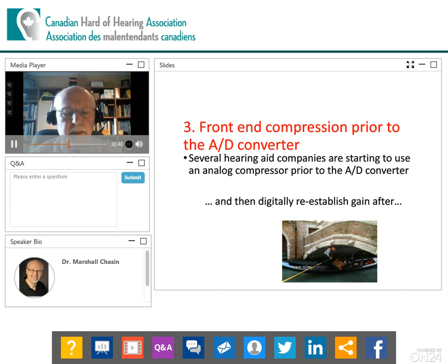So again, think of this as ducking under your bridge. And so you have front end compression. What that means is that it runs off the preamplifier of the microphone of your hearing aid. It reduces it. Compression means it reduces the sound, and puts it into the analog to digital converter. You digitize it. And then when it's in the hearing aid, it can put back what it did at the very beginning. And virtually all the hearing aid companies are using this technique. It's a low-tech innovation, but again, it's been around for many, many years.